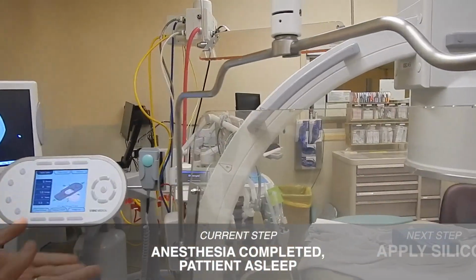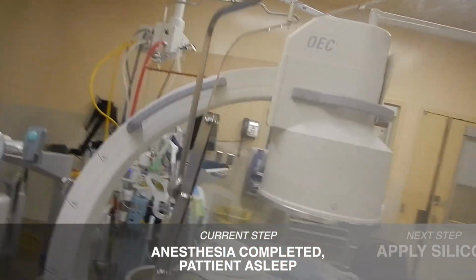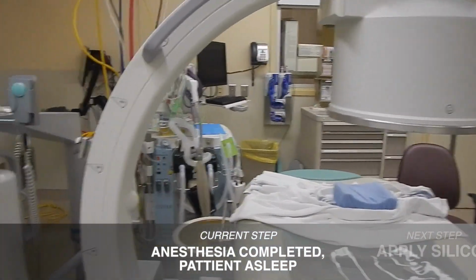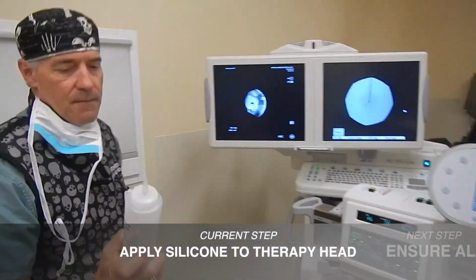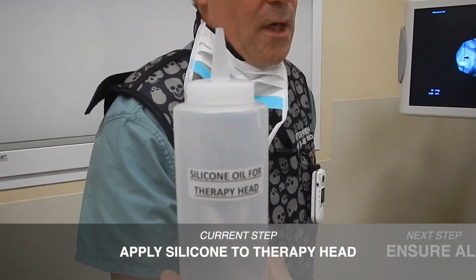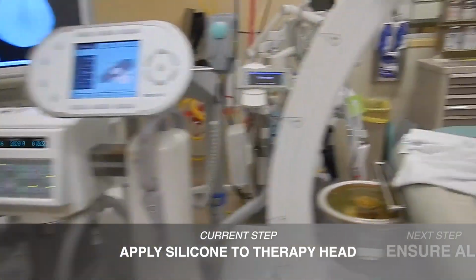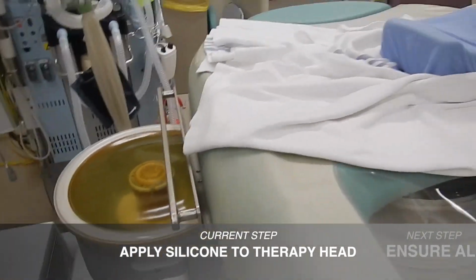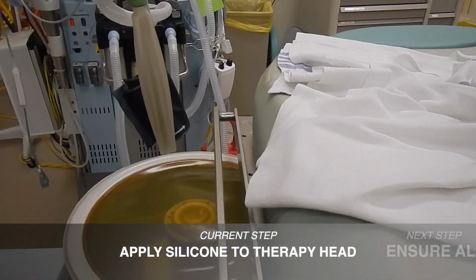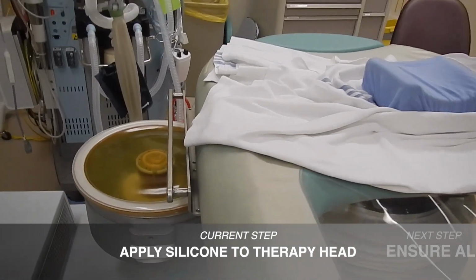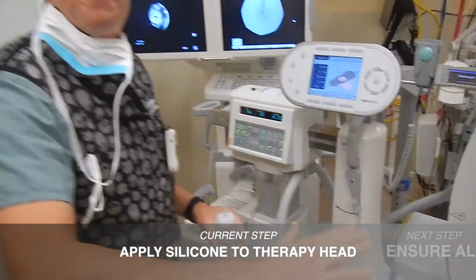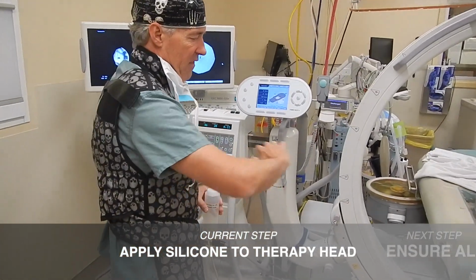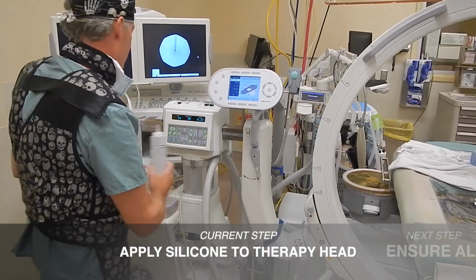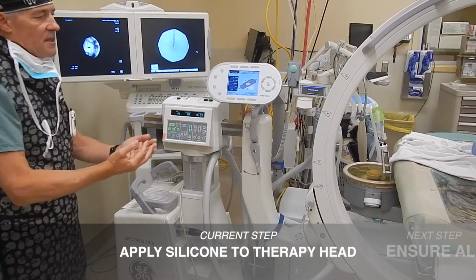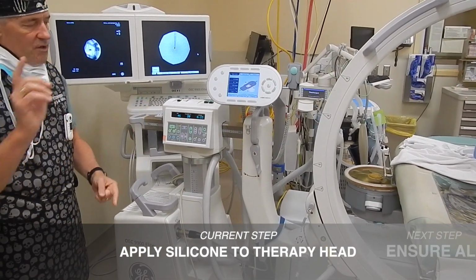Alright, so anesthesia does their thing. Patient's asleep now. While that was going on, a very important step has to take place. This silicone oil has to be applied to the therapy head. So you put a glove on, you reach over here, and you just squirt about this much, a toonie size or so, maybe a little more. Spread it around in your gloved hand. There's a thick coating of silicone oil on the therapy head, and that's for coupling to the table. And you'll see the next.